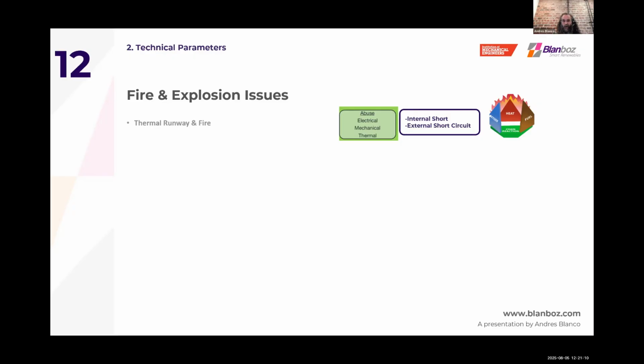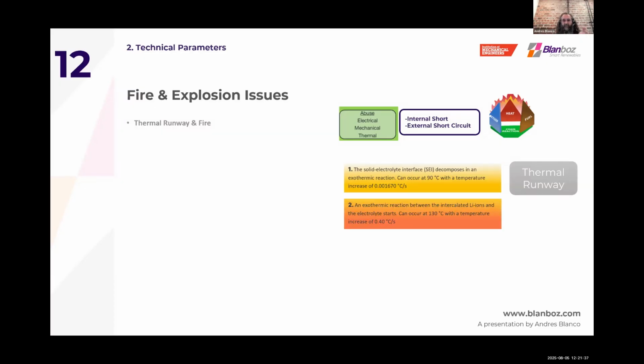Apart from discharging the battery, the thermal runaway goes through different stages. First, the SEI decomposes in an exothermic reaction, which can occur at 90 degrees with a temperature increase of about 0.001 to 0.0167 degrees Celsius per second, and you see the temperature start increasing quite fast.